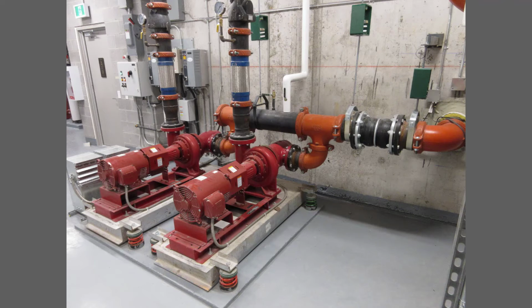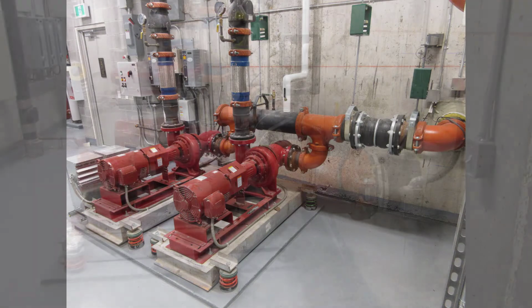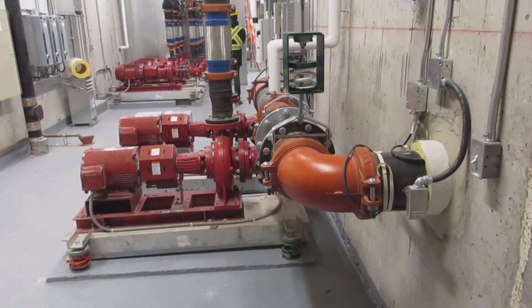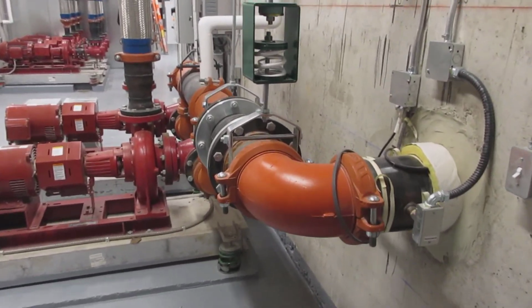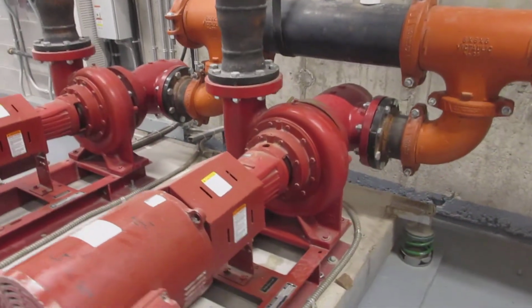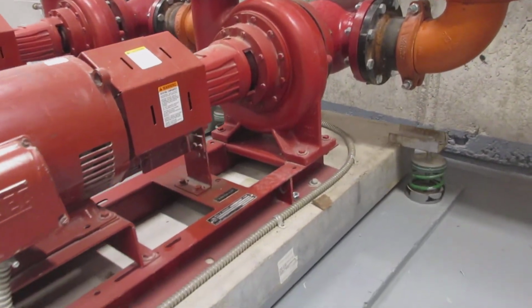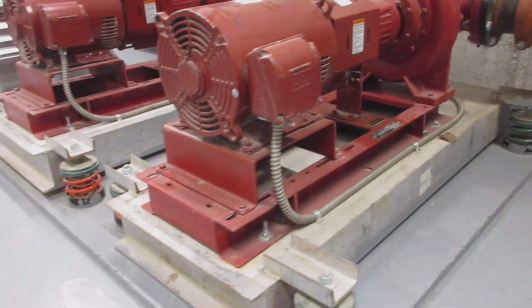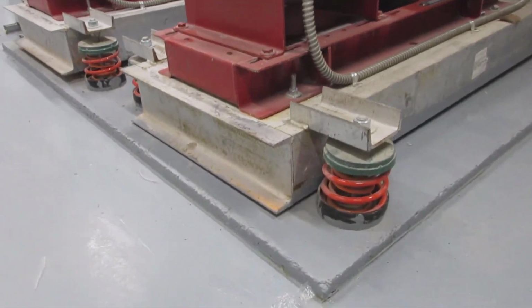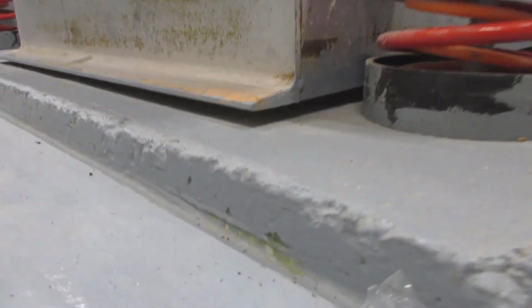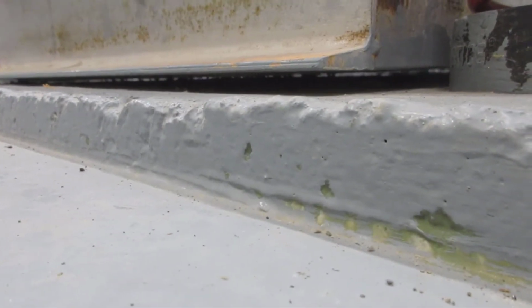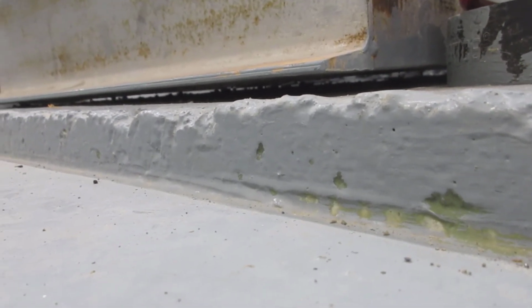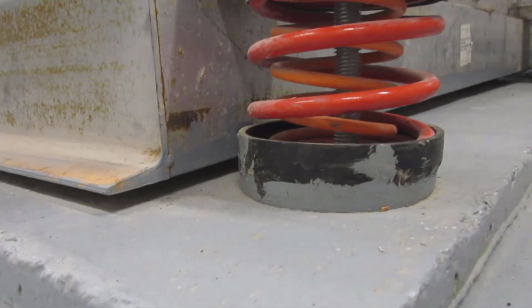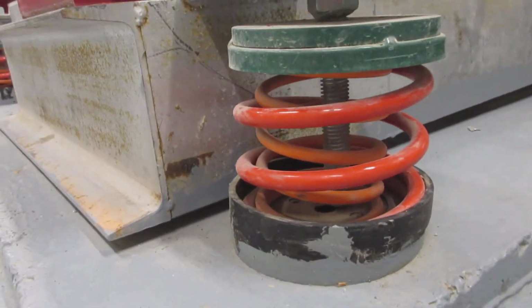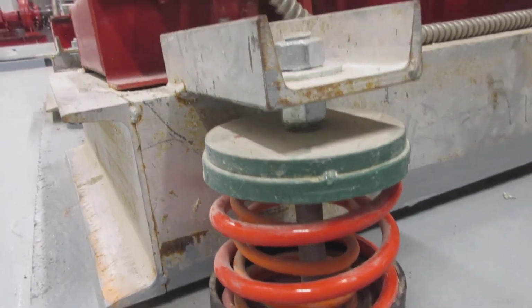We'll start the walk around on the right and take a closer look. This is the pipe bringing the water back from the cooling tower, located just outside the mechanical penthouse. It is connected to the inlet suction diffusers on these pumps, which are mounted on inertia bases on springs. The first thing I notice is that these bases appear a little too close to the ground. The gap appears to only be about half an inch at this corner. The isolator doesn't appear to be adjusted or to have much load on it. On a positive note, it is secured to the base.